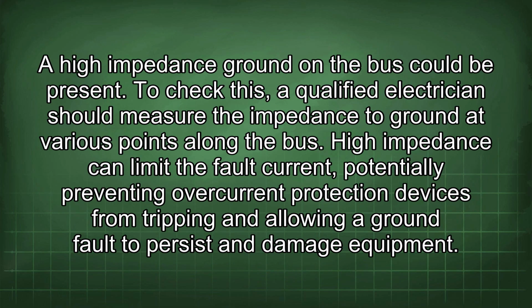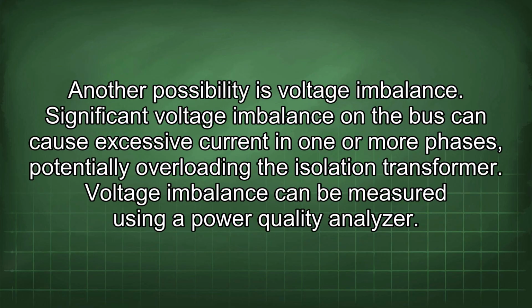A high impedance ground on the bus could be present. To check this, a qualified electrician should measure the impedance to ground at various points along the bus. High impedance can limit the fault current, potentially preventing overcurrent protection devices from tripping and allowing a ground fault to persist and damage equipment. Another possibility is voltage imbalance.